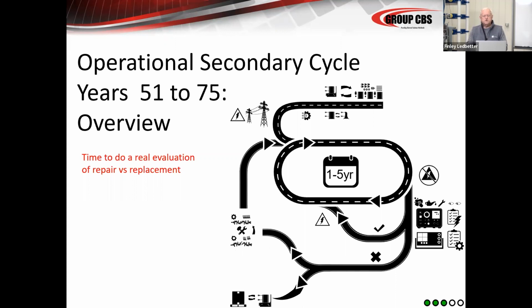The other thing that you might get is some arc resistant switchgear now that you didn't get in the last cycle. So in the last two cycles, the equipment that you got probably was not arc resistant. So you probably have to deal with PPE, hot zones or arc flash zones, remote racking, remote switching, that sort of thing, where the new equipment that you get in the next 25 to 50 years might deal with that problem internally. It might have onboard racking. It might be arc protected. There might be all sorts of things designed into it.